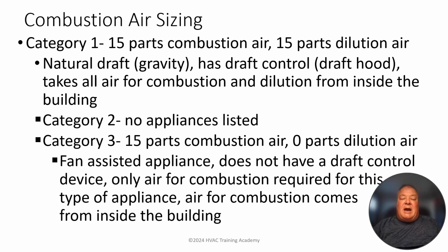They're all natural draft or gravitational type of exhausting devices. There's no fan at all incorporated in pushing the exhaust. It all happens through gravity and through hot flue gases rising. They all have draft hoods on them typically, and take all the air for combustion and dilution from inside the building. So all of those 30 parts are coming from inside the building.